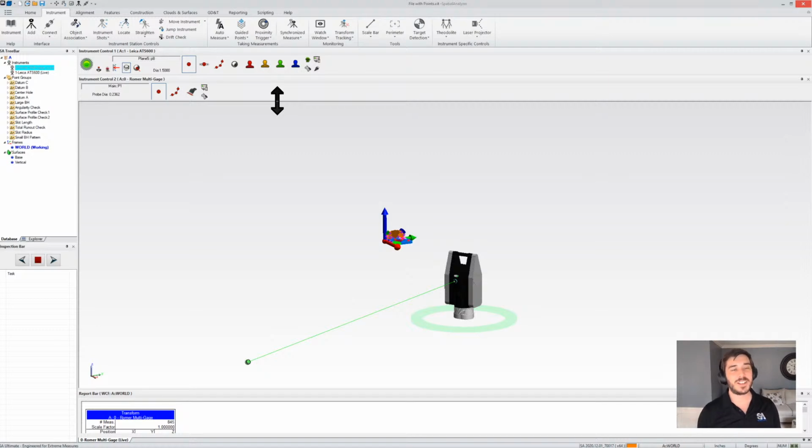And the way that that helps out is a laser tracker has really long distances that it can measure over, but an arm doesn't have to have line of sight in order to see things. So if you're measuring a part where you might have to measure inside of a cover or down below a surface, setting up a tracker to see a long distance and setting up an arm in that region where you need to see those out of line of sight items can be really helpful. And the way that most people do that is they'll measure 3 points with a tracker, and they'll measure those same 3 points with an arm, and then they'll both be tied into the same reference frame in SpatialAnalyzer, and then all the data is coordinated together in the software.